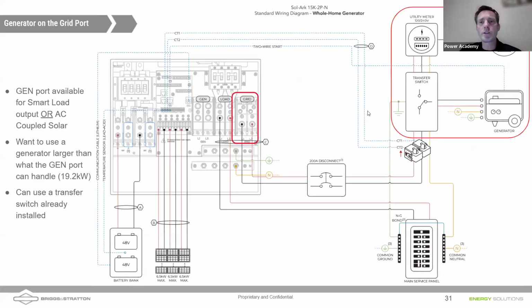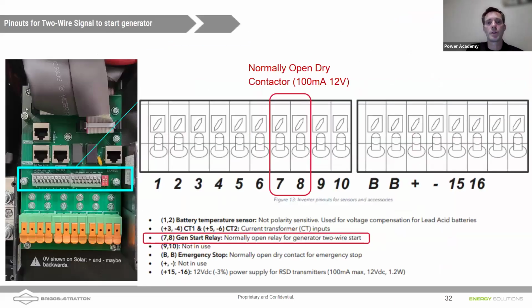And so you could also bring that generator in on a transfer switch. So if you want to integrate a generator into your ESS system, you could also use a transfer switch. And still that generator is going to stay off. That transfer switch is going to stay on grid until it sees power. And that power will stay off until that two-wire start gets triggered. So you're only going to be running that generator when those batteries are low enough to start a generator charge cycle, the settings that we showed earlier.